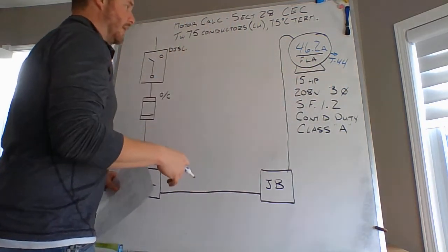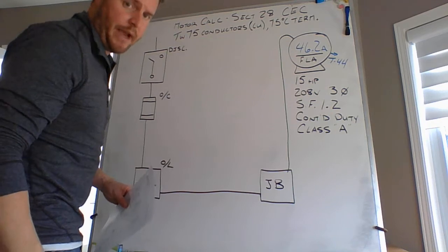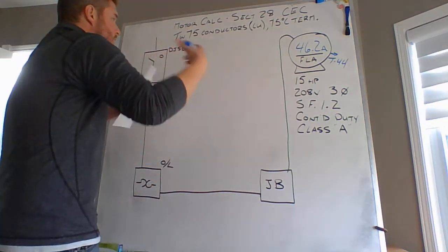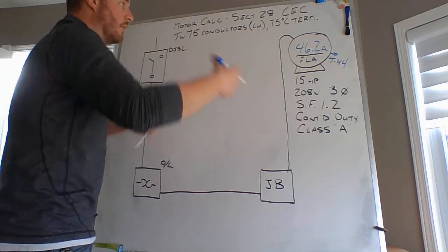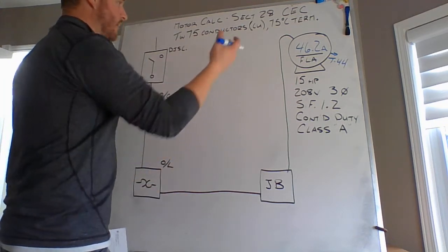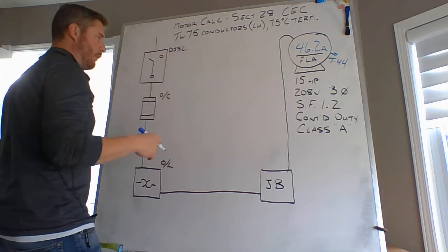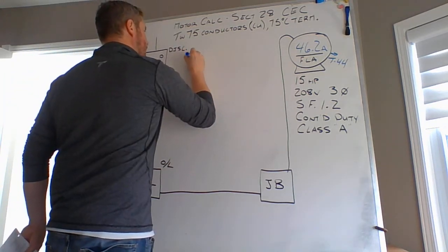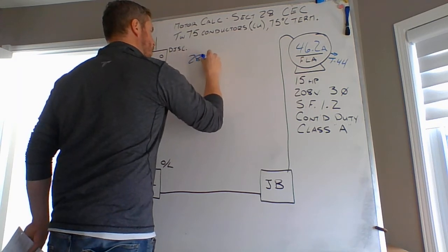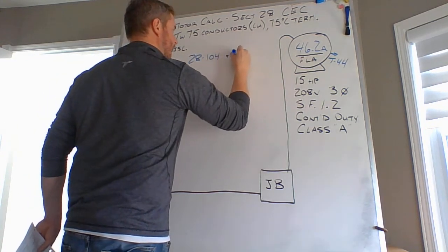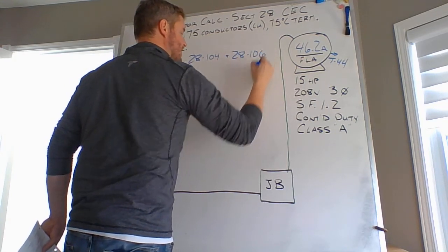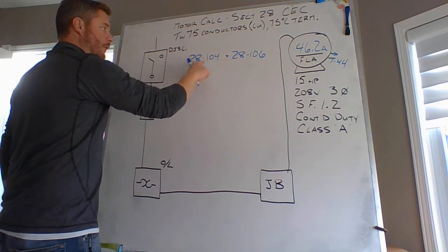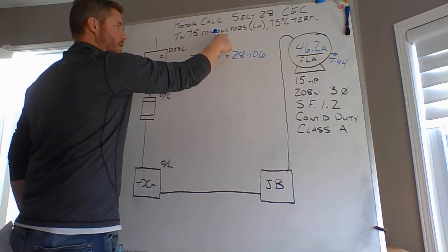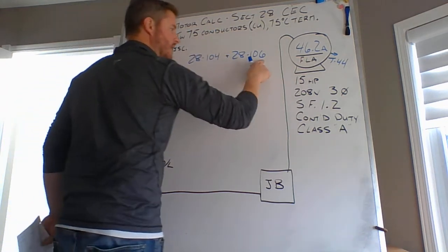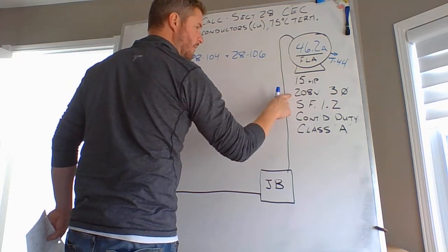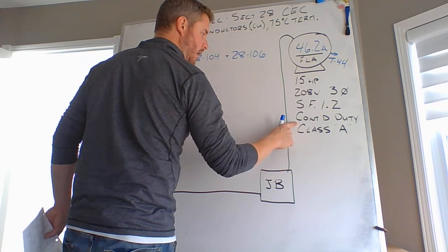The first direction that I would like to go is sizing my conductors and looking at what size of conductors I'm going to need to supply to this motor to deliver 46.2 amps as a full load current rating coming from my Table 44. Those rules are coming from Section 28, 104 and 28, 106. 28-104 talks about termination temperatures and installation ratings of conductors. 28-106 talks about the motor itself and the continuous duty service of that motor.